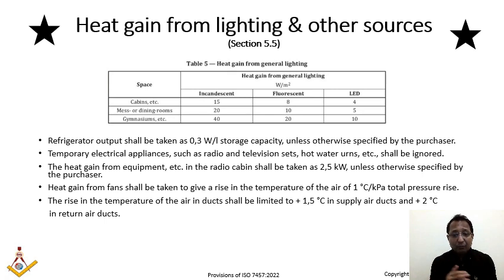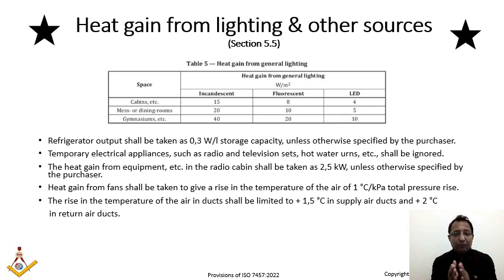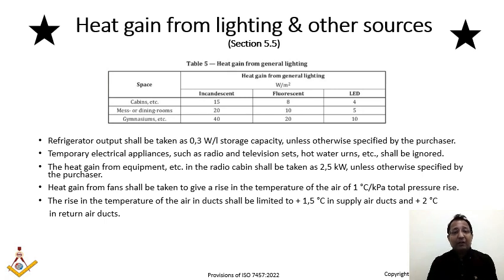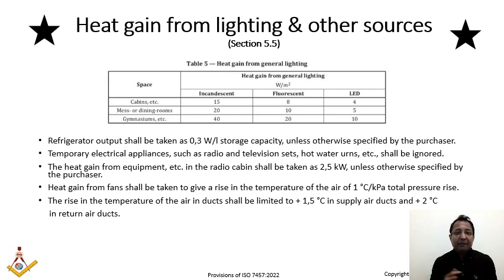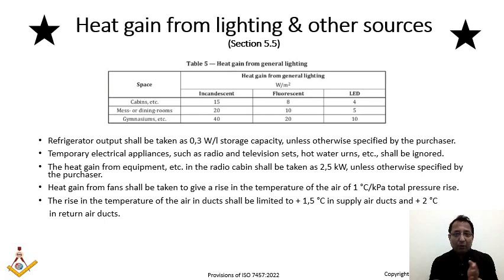The temperature rise limit is 1.5°C in supply ducts and 2.0°C in return air ducts. The apparatus dew point and supply temperature from heat load calculations — typically around 14°C — must account for this duct heat gain. When 14°C supply air enters a room maintained at 24°C, heat is picked up and returned to the duct. The coil must be sized to accommodate this delta T and match the required room conditions.